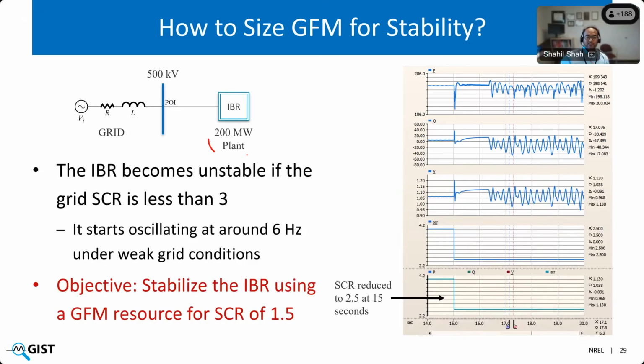Here is one 200 megawatt IBR, inverter-based resource, connected to the grid in single machine infinite bus format. And this particular IBR has a characteristic that it becomes unstable whenever the grid strength or short circuit ratio is less than 3. And that we can see in this time domain simulation. When the short circuit ratio is dropped to 2.5, the plant starts oscillating, it becomes unstable, and eventually it trips. Now, we want a specific objective. We want to size a grid forming BESS at this POI to stabilize this particular 200 megawatt IBR in a grid condition with SCR of 1.5.